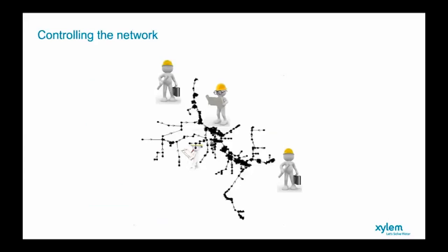So the way in which the rules are derived for the holistic control of the network uses what we call market-based optimization. And what this means is the rules are derived to follow cost curves. So the cost of flow being stored in one location is dependent on what's happening in the network as a whole. So if one of the data sensors records the level which indicates in this example that there's a problem, so this one's saying CSO30 is about to spill, something needs to happen, data from all the other sensors can then be consulted in a decision about what the cheapest solution is.